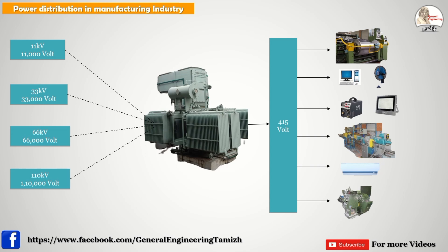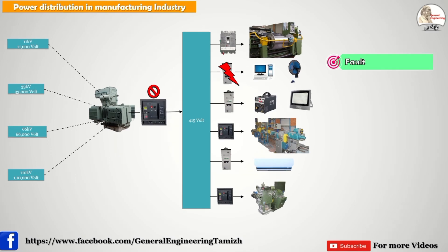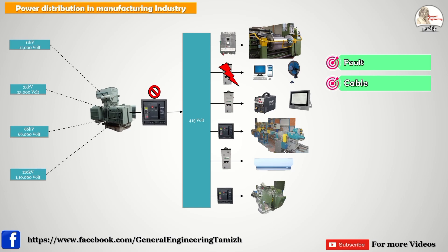The system is ready for simulation. The first scenario is fault. If any fault happens in the system — for example, this MCB has a short circuit fault — the fault current will affect the incoming breaker. If the incoming breaker trips, the total system power is disconnected and the plant is off. One small breaker fault can stop the total plant, which is definitely not a good power distribution system.